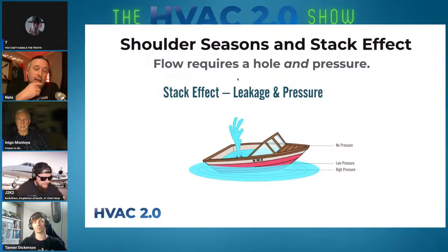So seeing that half the year is relatively moderate in temperatures, the next step to look at is shoulder seasons and stack effect. Now, to get flow, you don't just need a hole, you need a hole and pressure. And this is the challenge that we have in shoulder seasons. So if you think of a boat and pressure, if you have a hole above the water line, is that going to leak much? No, there's hardly any pressure. So only when a wave laps up over it is any water going to come in. So you're not going to get a lot of flow.